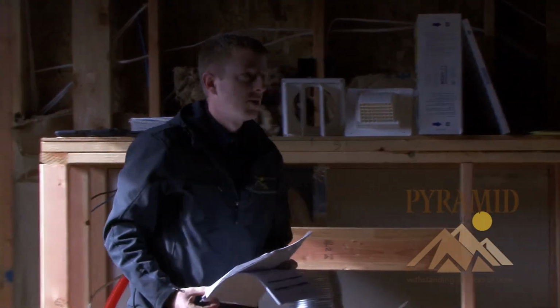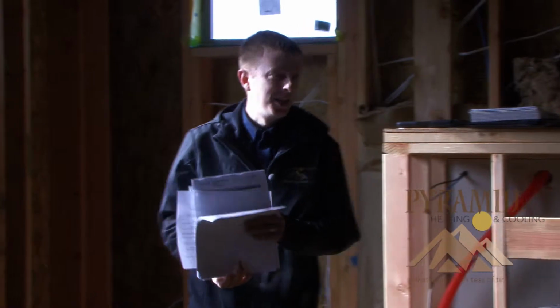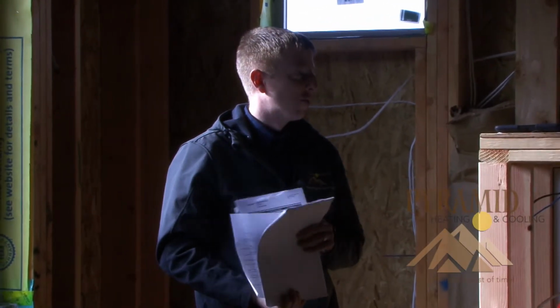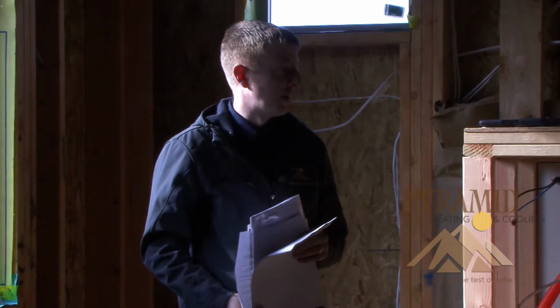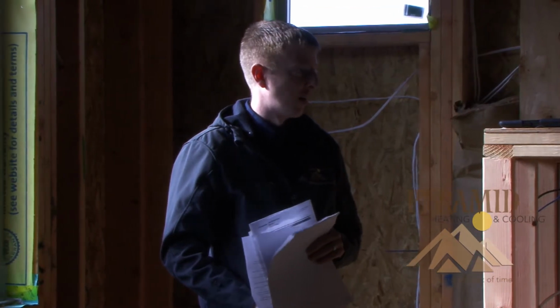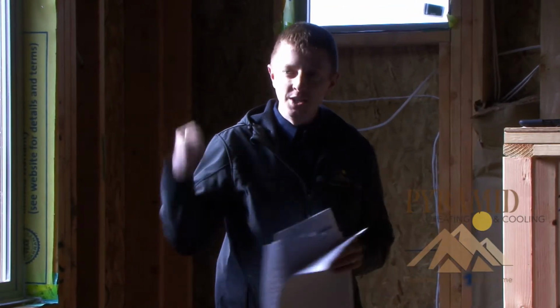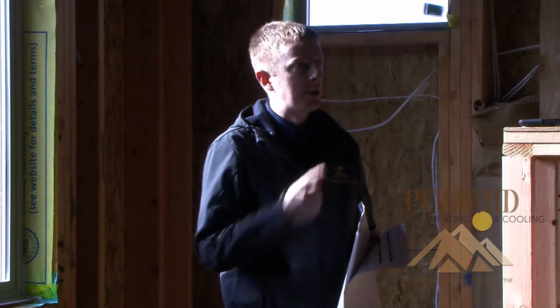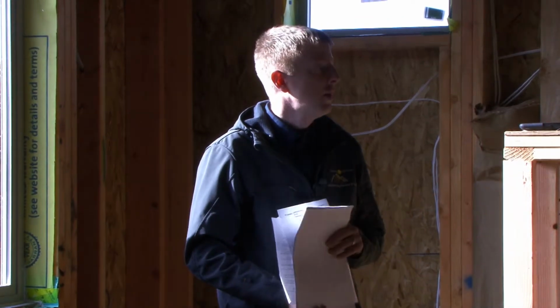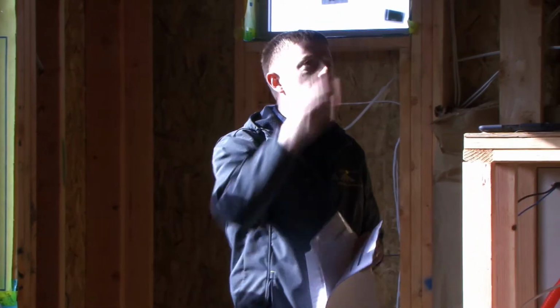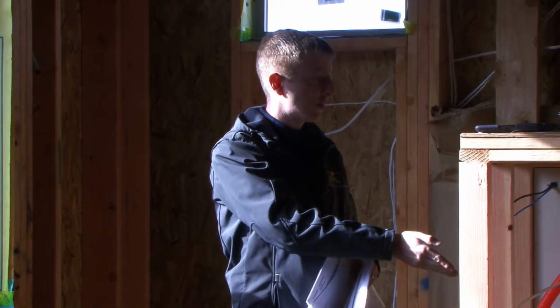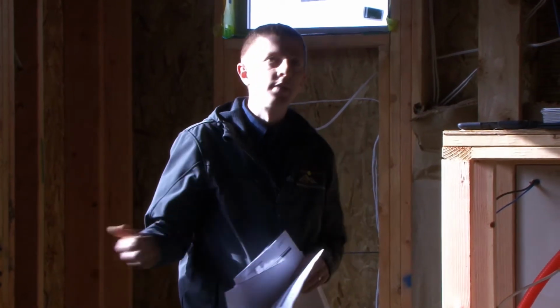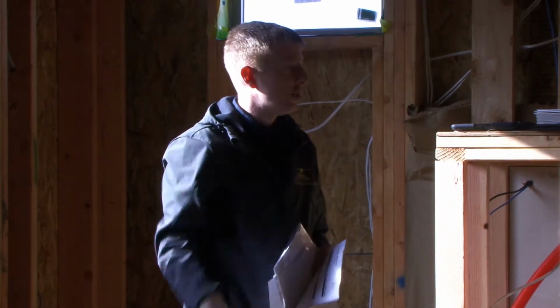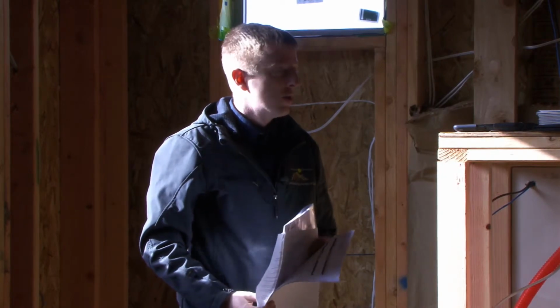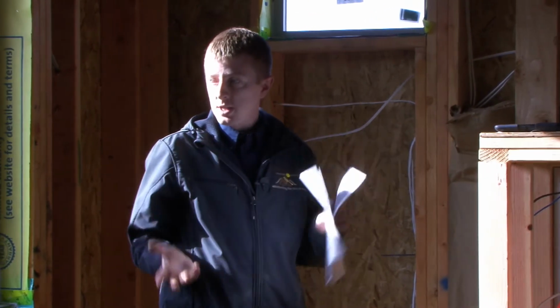You see the gray paint on the ductwork? That's water soluble. How well do you think that stays on with a house with no roof when the ducting's in the crawl space? It washes back off. So in the initial test, it passes. We get some rain, it washes back off. Until it hardens, it's water soluble. So with this, the integrity stays the same at the install as it does at the test out, as it does years from now when this is sheetrocked and inaccessible. So those are some of the benefits of just the ducting portions.